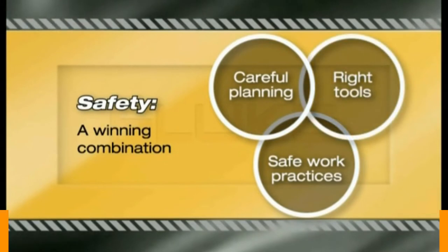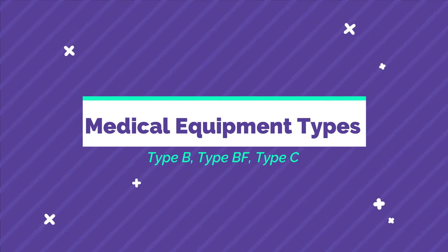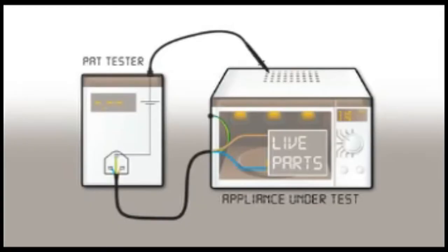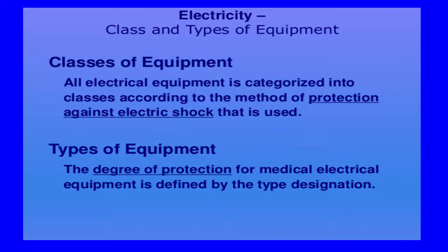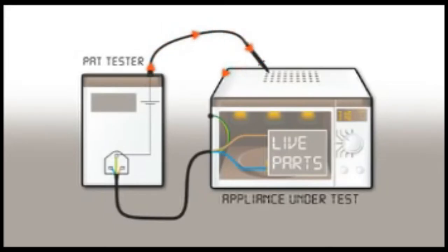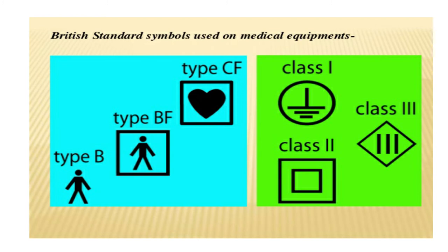In this last video, we will cover the Medical Equipment Type. The class of equipment defines the method of protection against electric shock. The degree of protection for medical electrical equipment is defined by the type designation. The reason for the existence of type designations is that different pieces of medical electrical equipment have different areas of application, and therefore different electrical safety requirements.